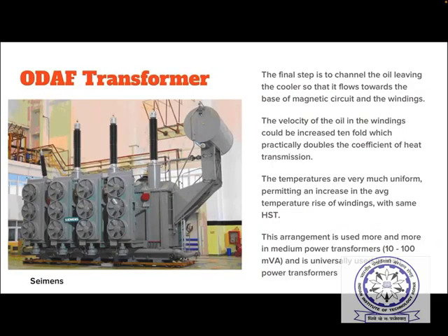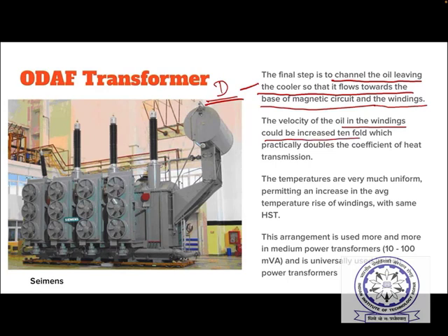Then the next one, the final one, is ODAF transformer. The final step is to channel the oil leaving the cooler so that it flows towards the base of magnetic circuit and the windings. So instead of allowing it to flow freely in whichever direction it flows, if we channel the oil leaving the cooler so that it flows towards the base of the magnetic circuit, then that is what is known as directed flow of the oil. The velocity of the oil in the windings now could be increased around 10 times, and this practically doubles the coefficient of heat transmission. This is very, very important.